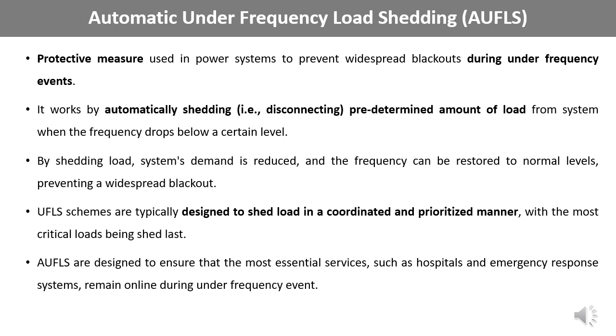UFLS is designed to ensure that the most essential services, such as hospitals and emergency response systems, remain online during under-frequency events. It helps to prevent voltage instability, loss of synchronization, overloading of equipment, tripping of protective devices, islanding scheme operation, cascading failures, and other problems that can occur during under-frequency events. UFLS is an essential protective measure that power system operators use to prevent widespread blackouts during under-frequency events — it works by automatically shedding load in a coordinated and prioritized manner, ensuring that critical services remain online.